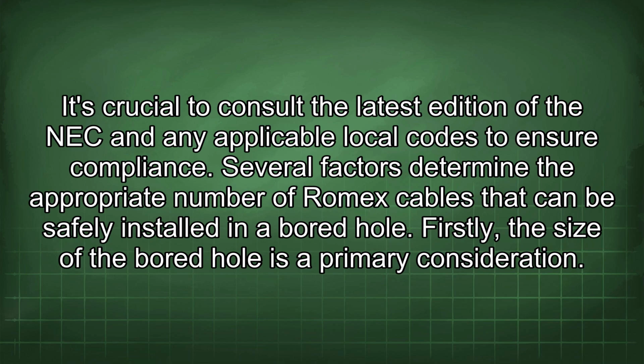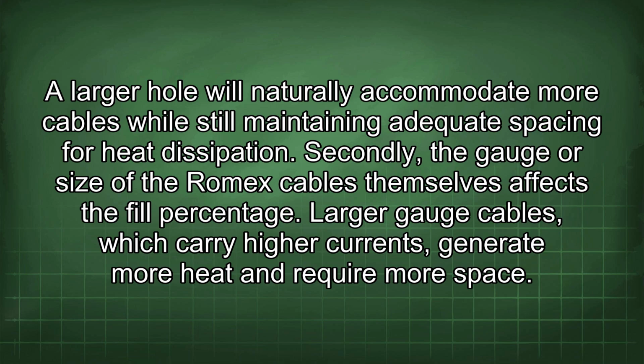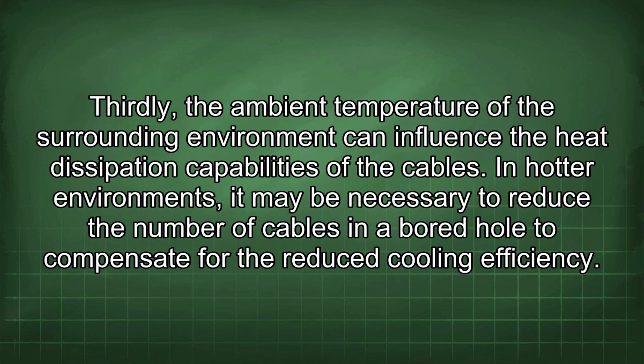Several factors determine the appropriate number of Romex cables that can be safely installed in a bored hole. Firstly, the size of the bored hole is a primary consideration. A larger hole will naturally accommodate more cables while still maintaining adequate spacing for heat dissipation. Secondly, the gauge or size of the Romex cables themselves affects the fill percentage. Larger gauge cables, which carry higher currents, generate more heat and require more space. Thirdly, the ambient temperature of the surrounding environment can influence the heat dissipation capabilities of the cables.